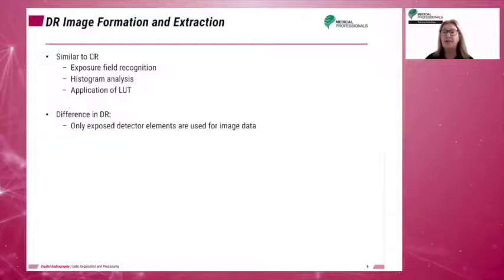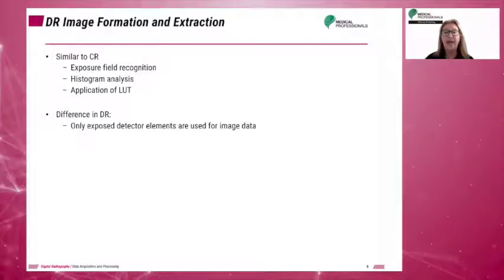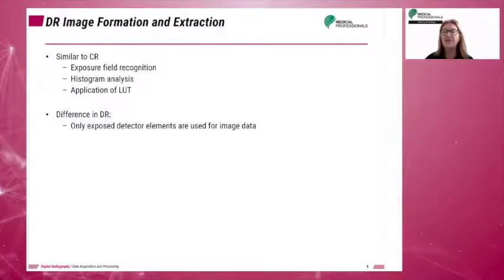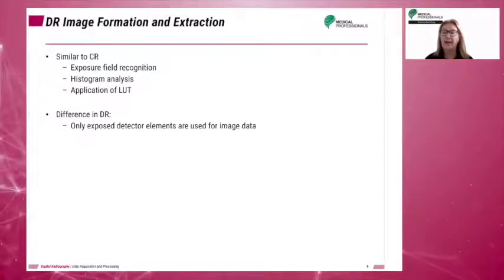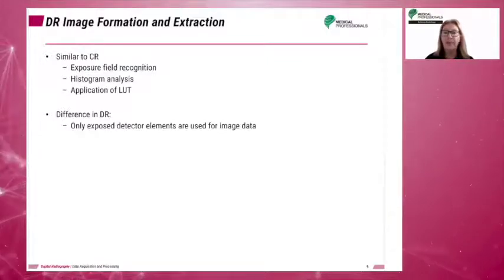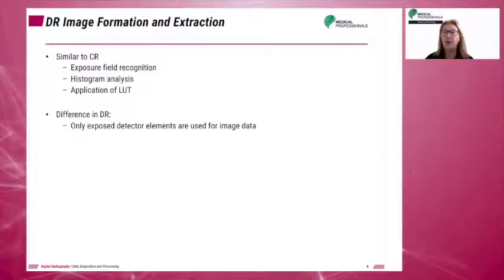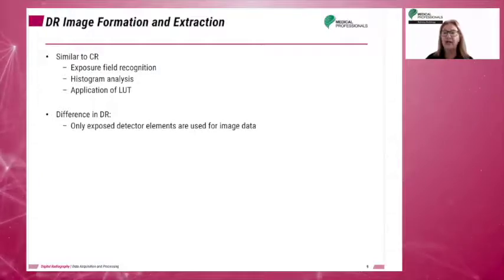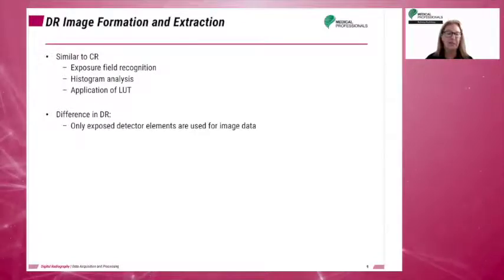At this point, all three DR systems go through the same process as CR to produce the display image. The histogram is created and analyzed, the exposure field is recognized, histogram analysis occurs, and the lookup table (LUT) is applied for rescaling of the data prior to display. With DR systems, only the detector elements that were exposed contribute to the formation of the image displayed on the monitor.